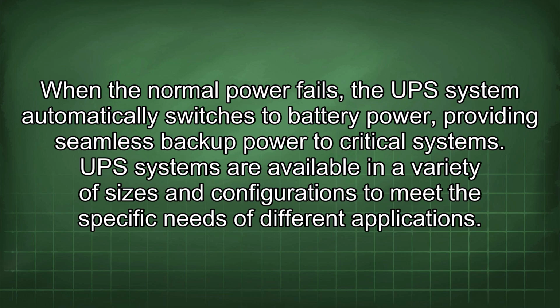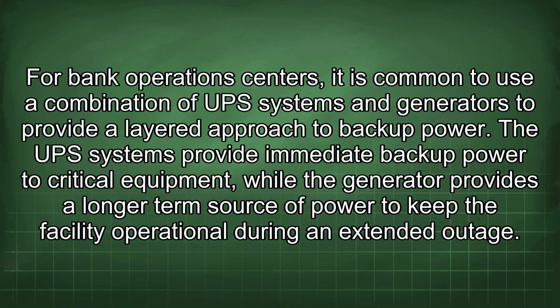UPS systems are available in a variety of sizes and configurations to meet the specific needs of different applications. For bank operations centers, it is common to use a combination of UPS systems and generators to provide a layered approach to backup power. The UPS systems provide immediate backup power to critical equipment, while the generator provides a longer-term source of power to keep the facility operational during an extended outage.